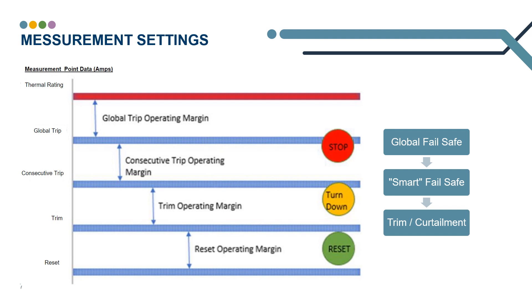We have another trip function set below the global trip called the consecutive trip. This is designed to avoid a global trip of the whole system and will trip the sites lowest in the stack, or most relevant to the constraint, in an effort to prevent that global trip. We don't want to trip generators, and that's why we have a trim margin set below the aforementioned trip values. If the measurement point goes above the trim threshold, curtailment is going to be sent to the generators in order of the LIFO stack. Generators will then scale back and in theory avoid any of the wider trips. Measurement points will release capacity once the recorded values go below the reset value.